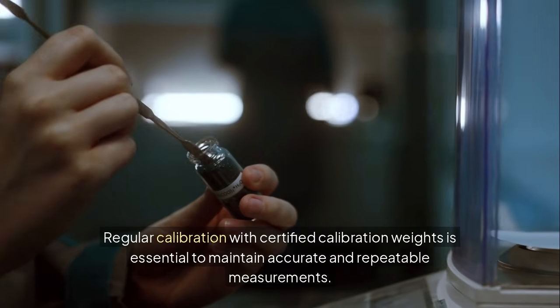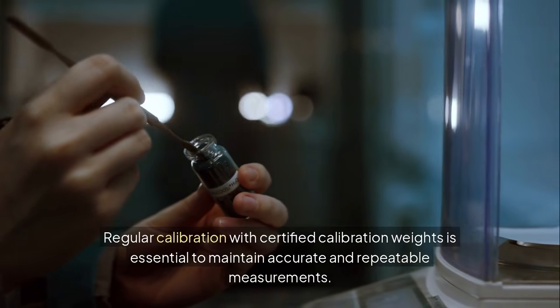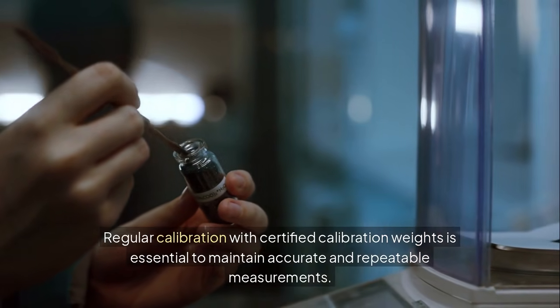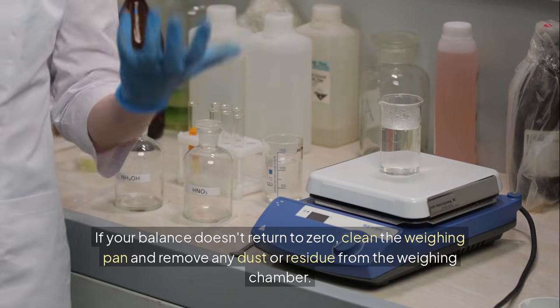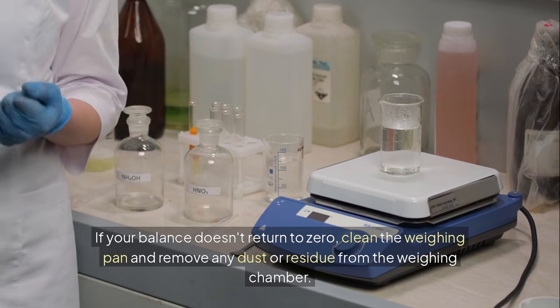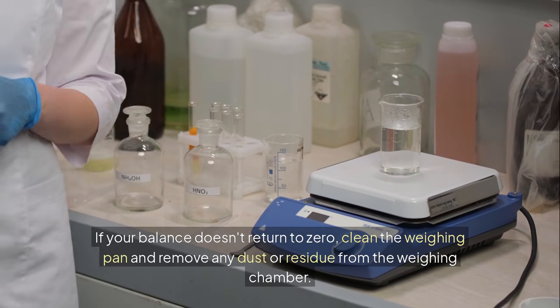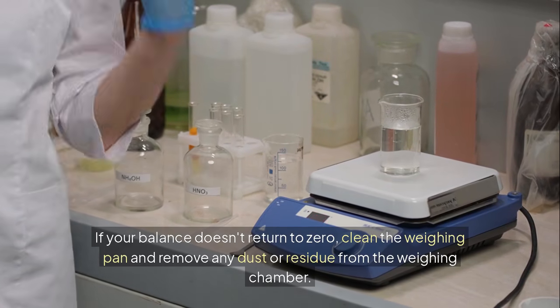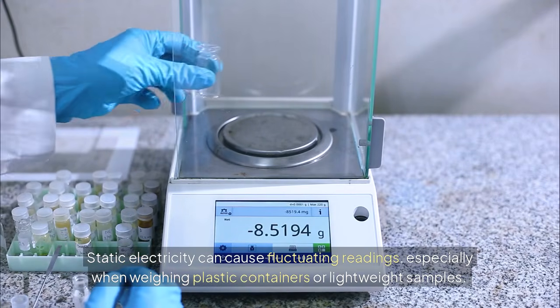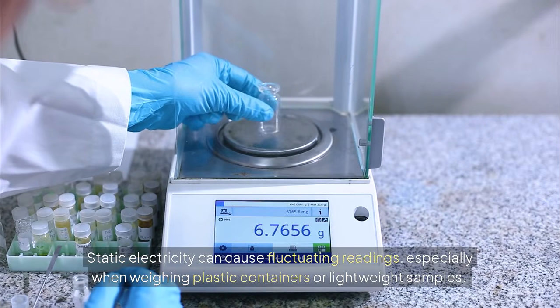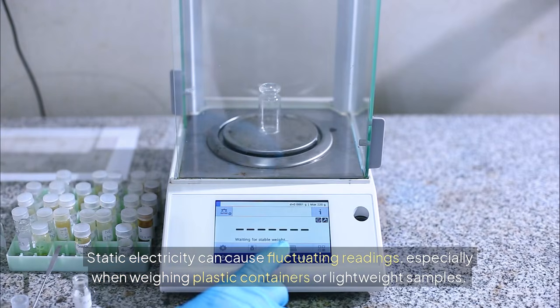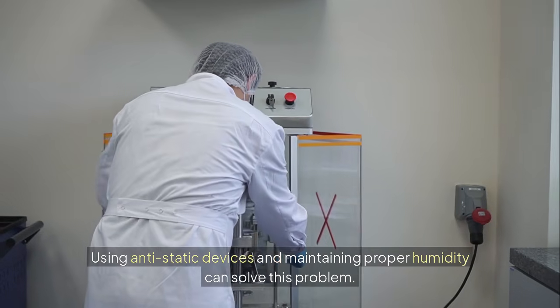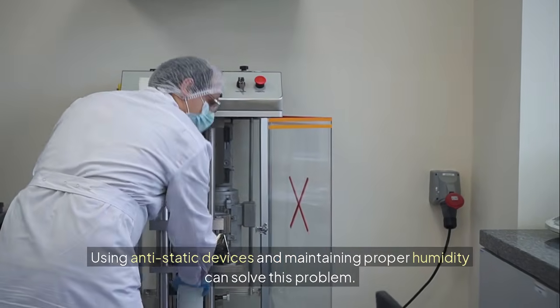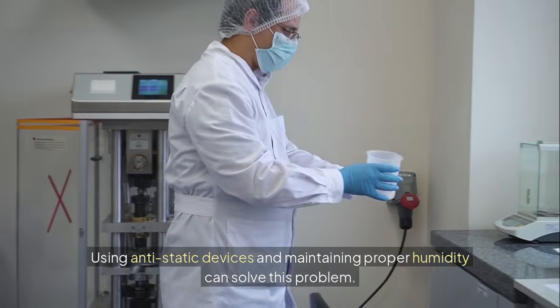Regular calibration with certified calibration weights is essential to maintain accurate and repeatable measurements. If your balance doesn't return to zero, clean the weighing pan and remove any dust or residue from the weighing chamber. Static electricity can cause fluctuating readings, especially when weighing plastic containers or lightweight samples. Using anti-static devices and maintaining proper humidity can solve this problem.